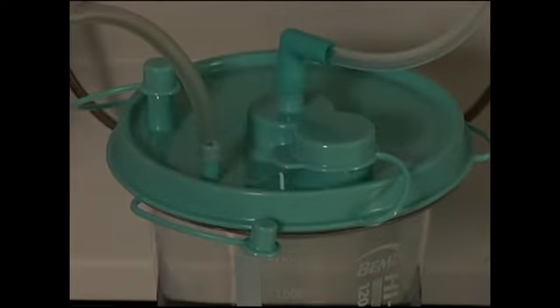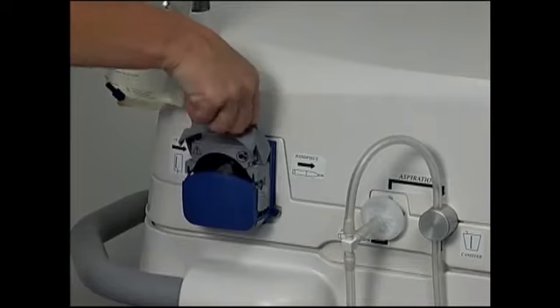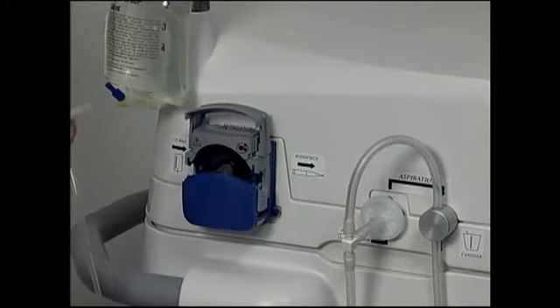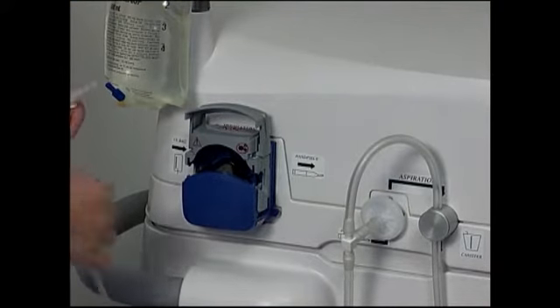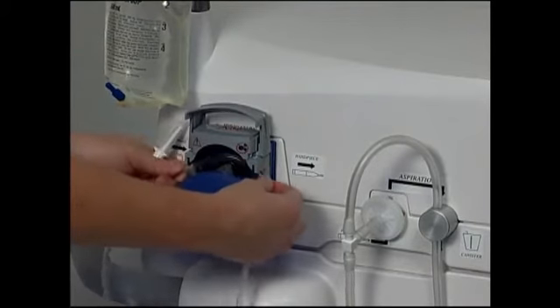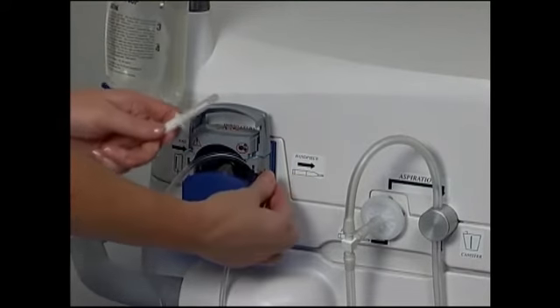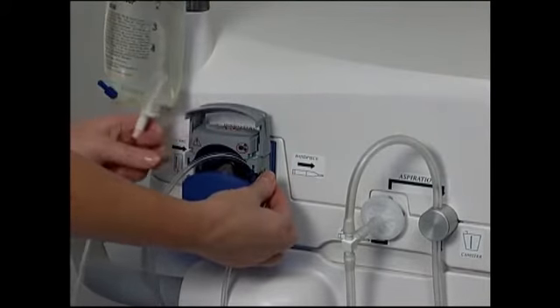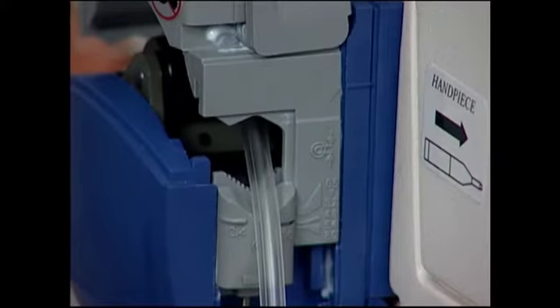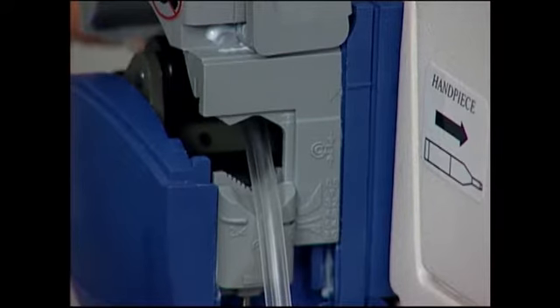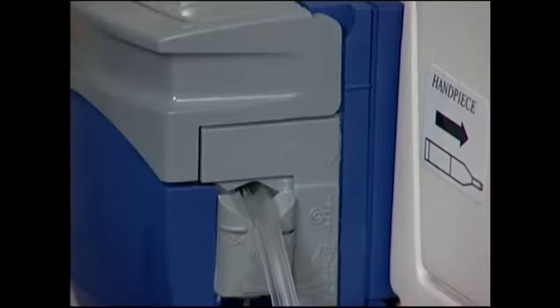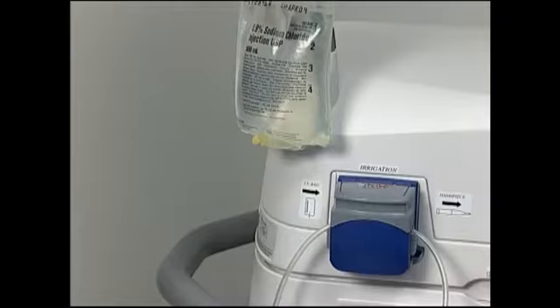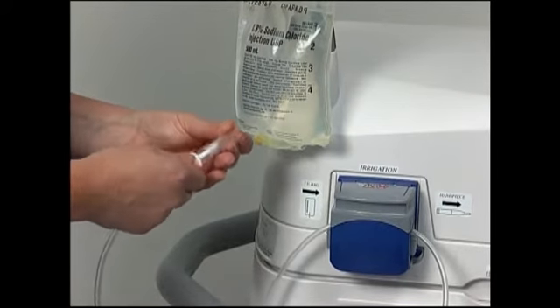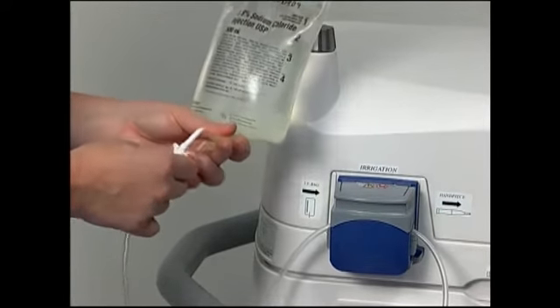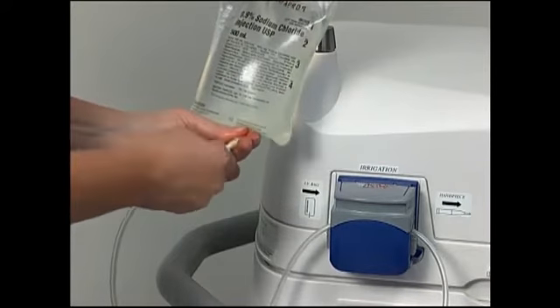To route the smaller irrigation tubing, first unclip the latch of the peristaltic irrigation pump. Place the IV tubing over the roller of the pump. The spiked and capped distal end will exit the top of the pump next to the irrigation pole. Ensure that the tubing is aligned with the V-shaped notches of the upper part of the pump head and close the latch. Remove the cap from the spike on the irrigation tubing and spike the IV bag.